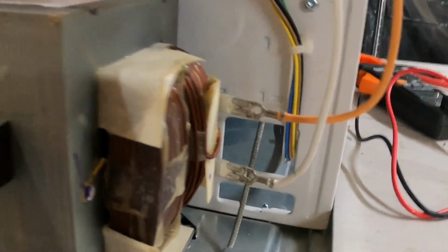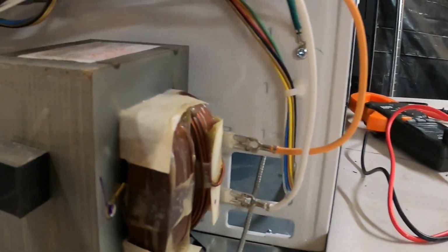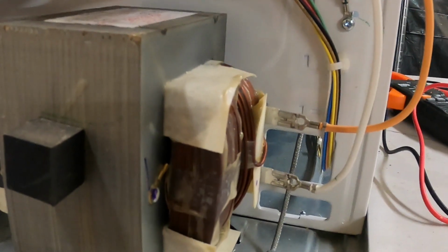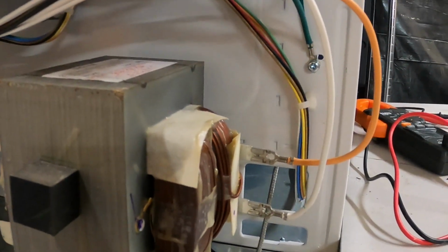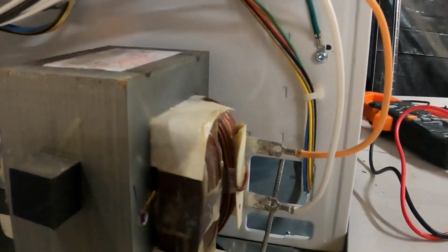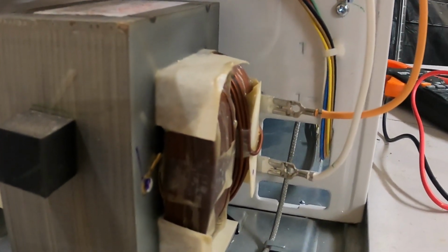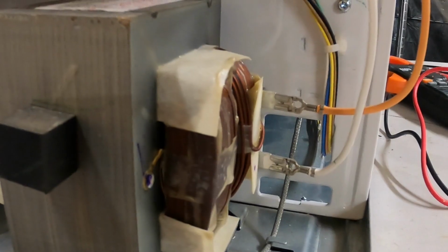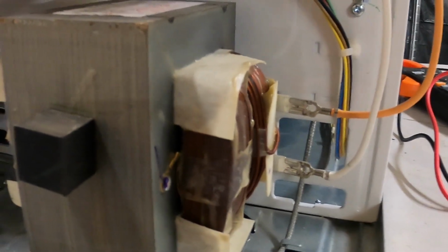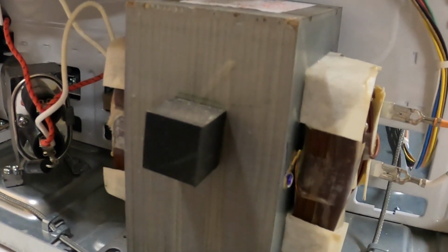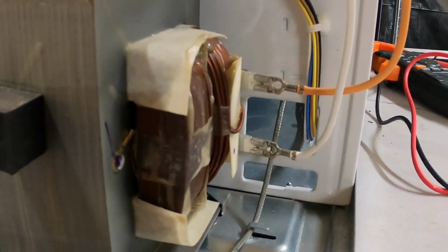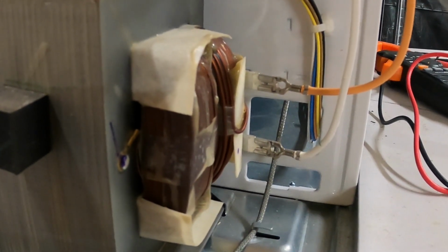So the first thing you have to do, if you're unsure of what's going on, is determine if the problem is a high voltage issue or a low voltage issue. Here we have what's called your high voltage transformer. You see the orange and white wires in, that's your primary. Over here, you see the two white wires with the red wire. That's your secondary and your filament voltage.